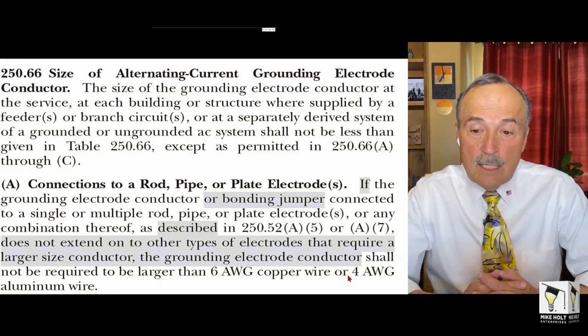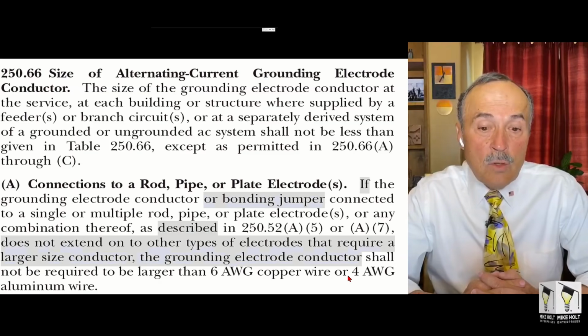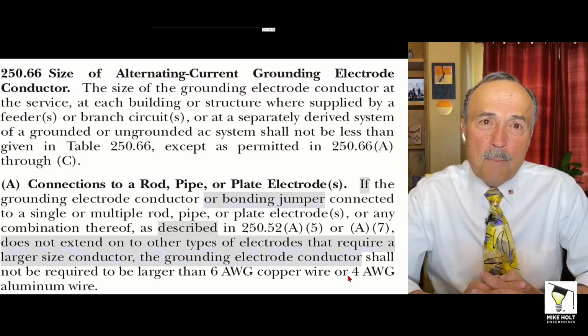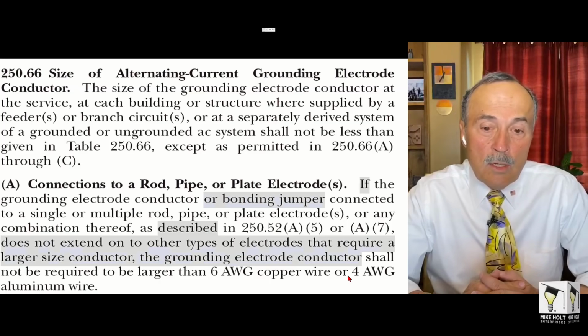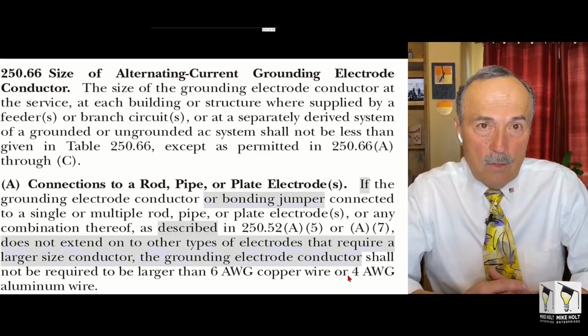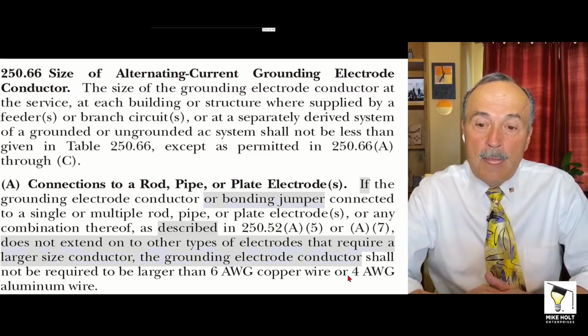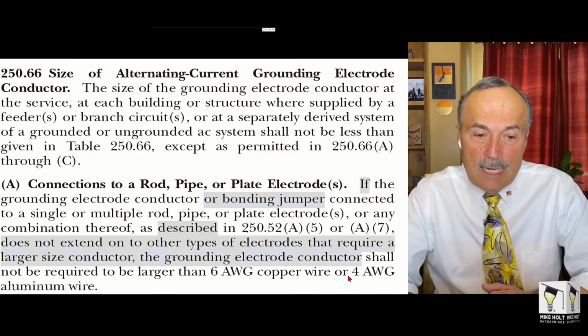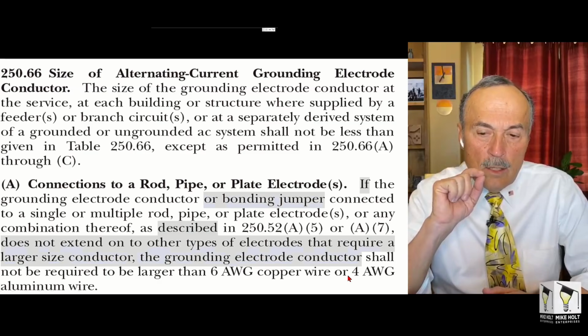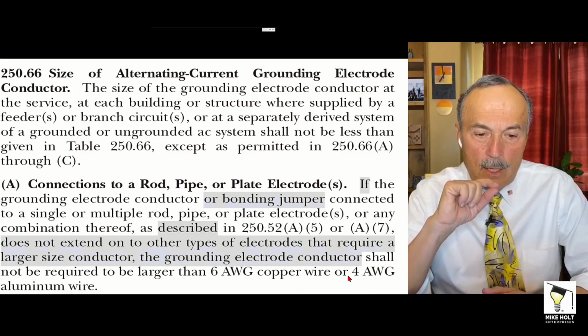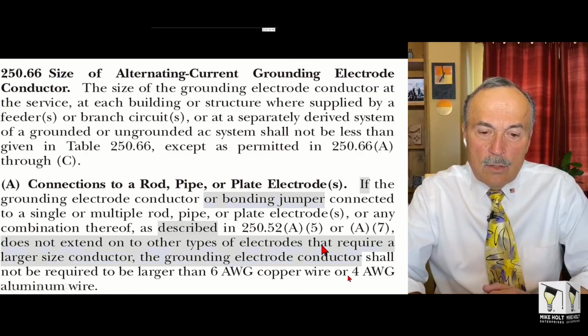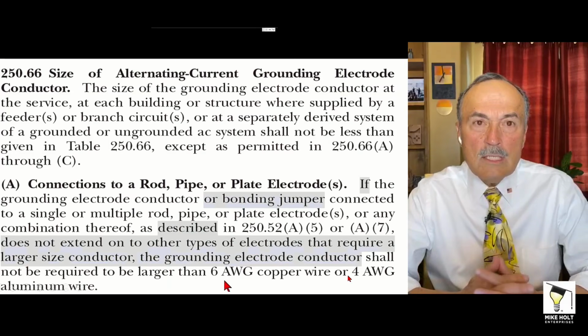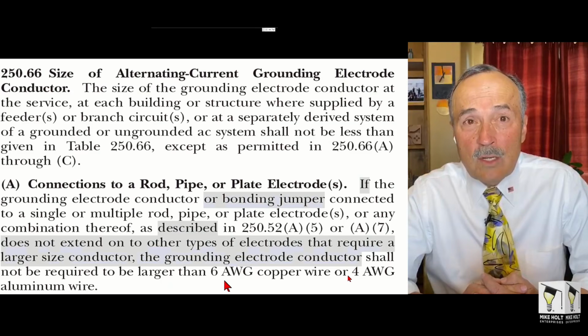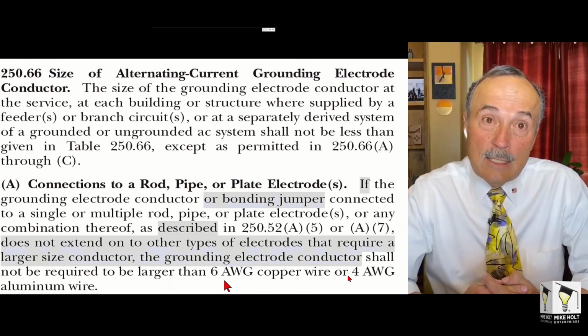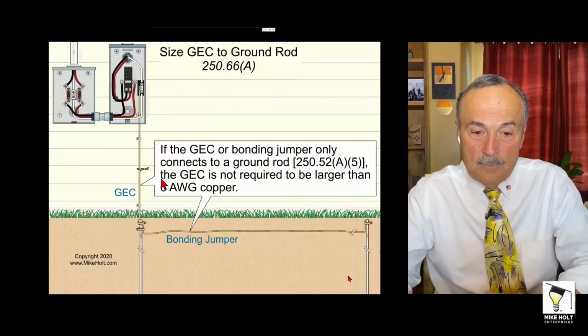So what does 250.66(A) say? Connections to a rod, pipe, or plate electrode. Probably we're not putting pipes in the ground and making that an electrode anymore. We're not putting plates in the ground, making that an electrode anymore. We're just going to put a rod. If the grounding electrode conductor or bonding jumper is connected to a single or multiple rod or any combination of them, and it does not extend to other types of electrodes that require a larger size conductor, the grounding electrode conductor should not be required to be larger than 6 gauge. I think they kind of screwed the language up in the 2020 code. Let me tell you what it said, and let me tell you what it says, even though it doesn't seem that way. It says this.